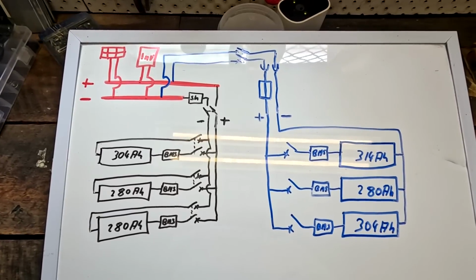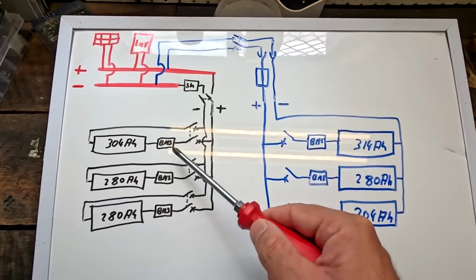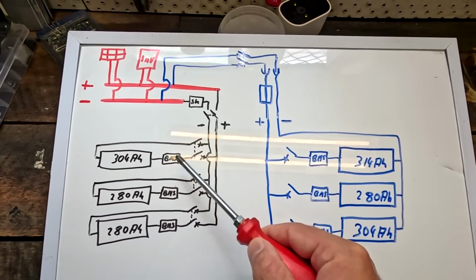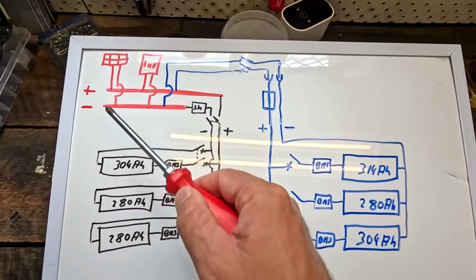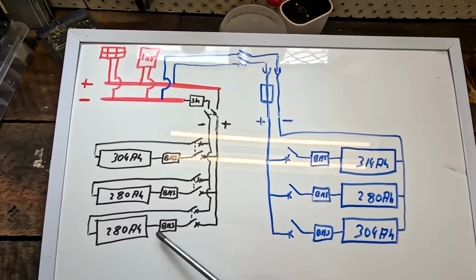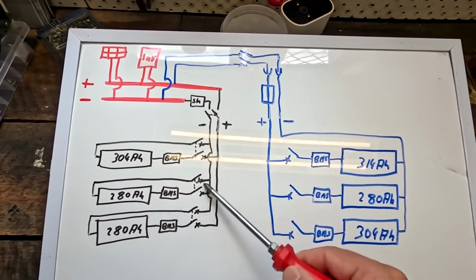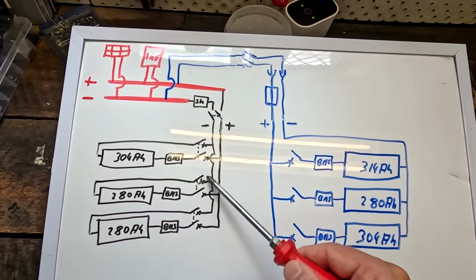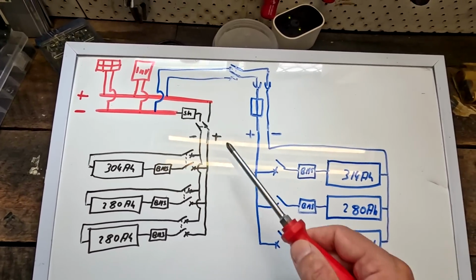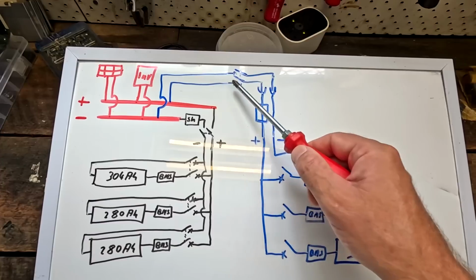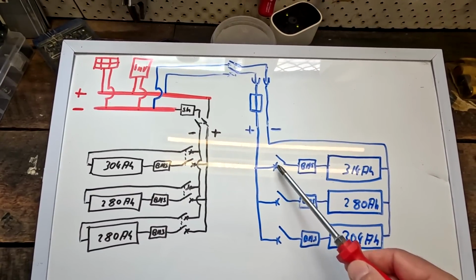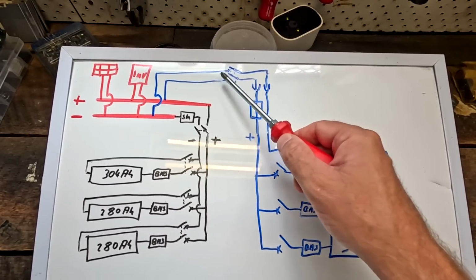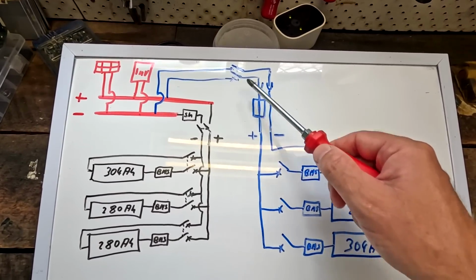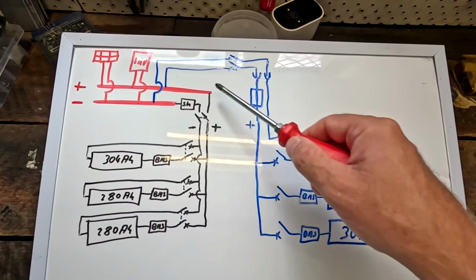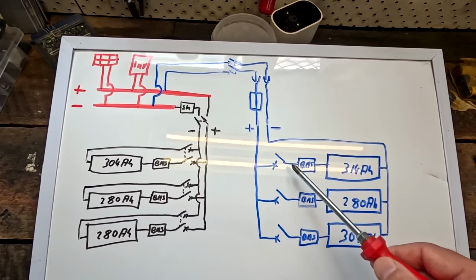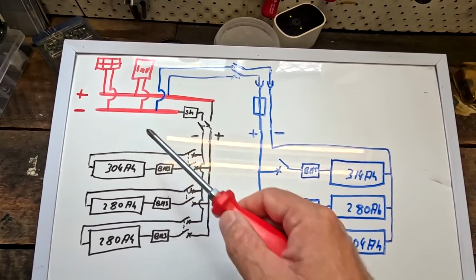So, with everything connected this way, you'd assume this battery here gets most of the power because it's closest to the solar charge controllers. This one gets less, this one gets less, because there's a certain voltage drop across all this equipment and the bus bar system. And further still, these batteries here get even less power because the resistance of all these connections, the additional fuse, circuit breaker, Anderson connectors, and the longer cable run to the MPPT solar charge controllers all add up.